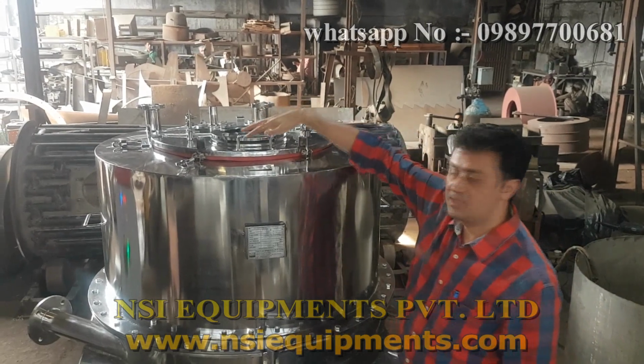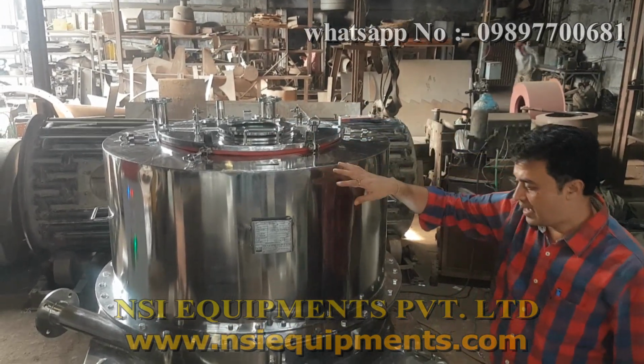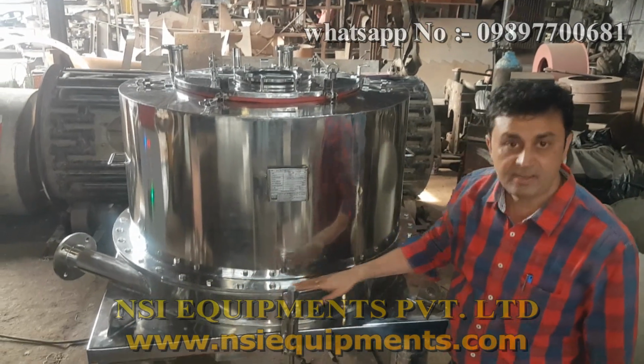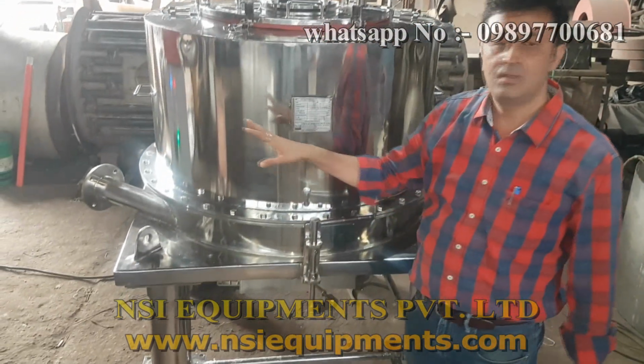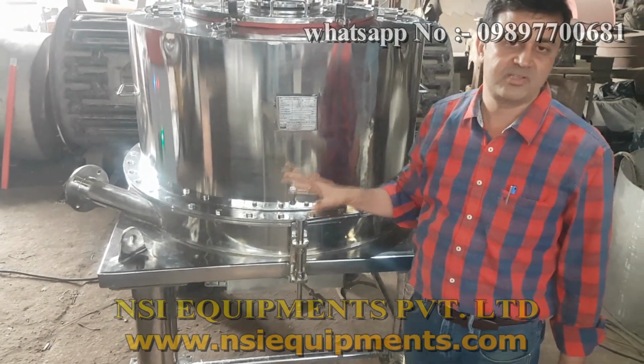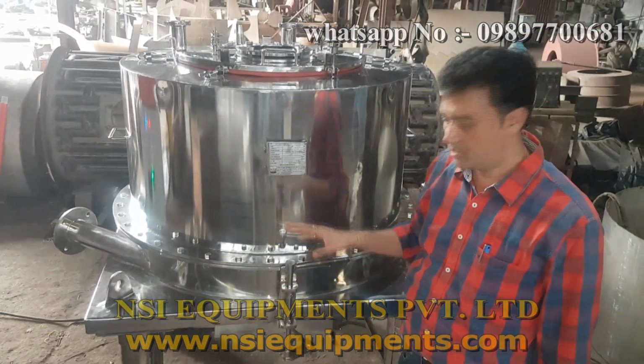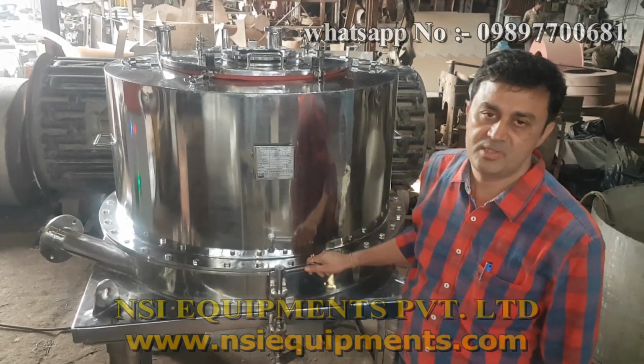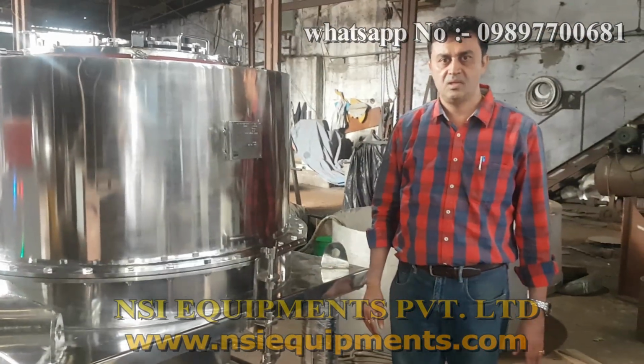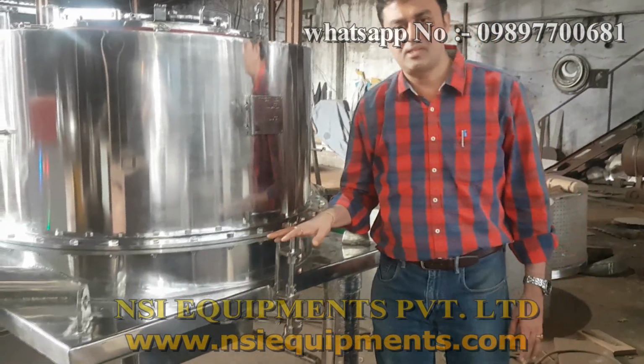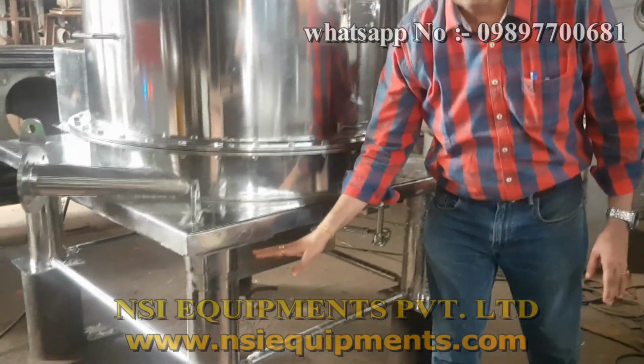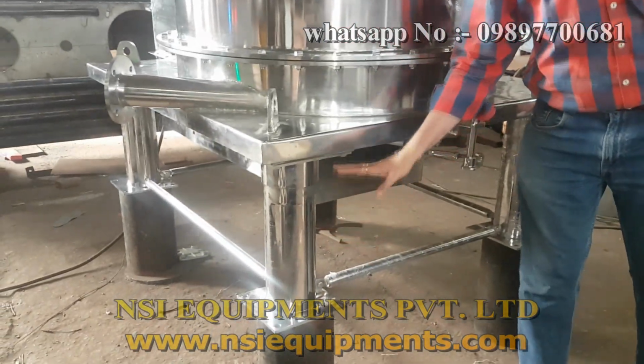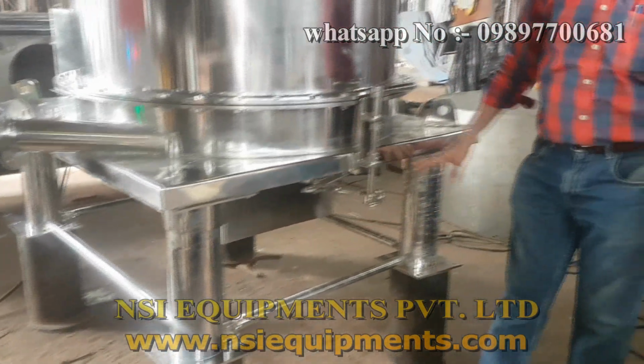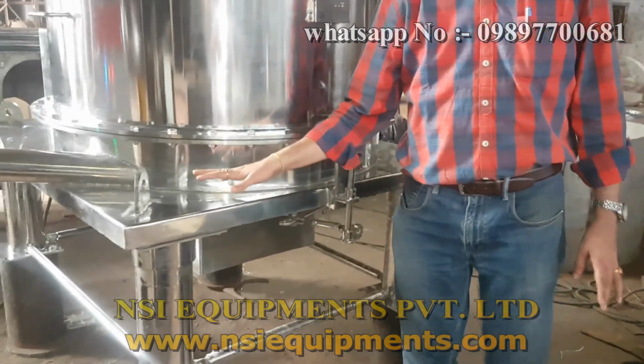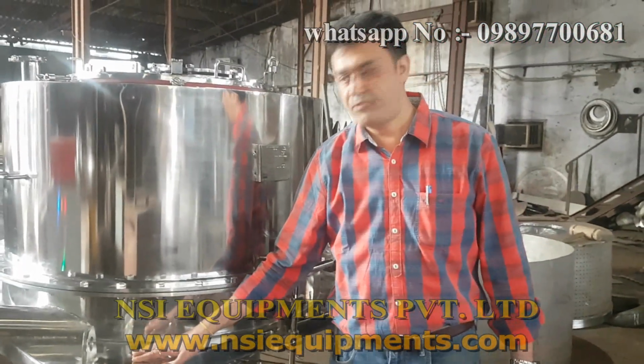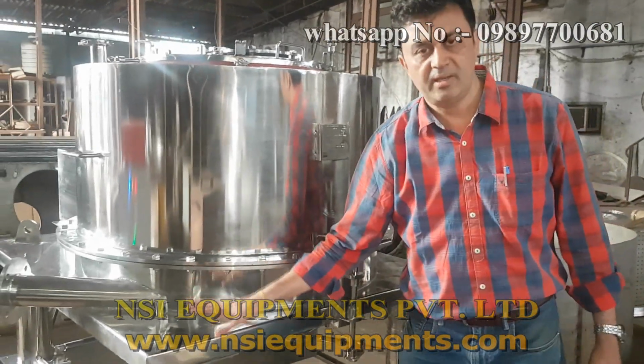This is the sight glass, this is the top cover, and this is the manual braking system. This consists of a VFD drive system with the reverse current braking. However, we are providing mechanical brakes also for emergency stopping. As you can see, this is a 4-point suspension centrifuge, and this is a visco damper, an anti-vibration mounting. All the 4 mounts, you can see, take up any uneven unbalance of the centrifuge, and this is mounted on the inertia plate.